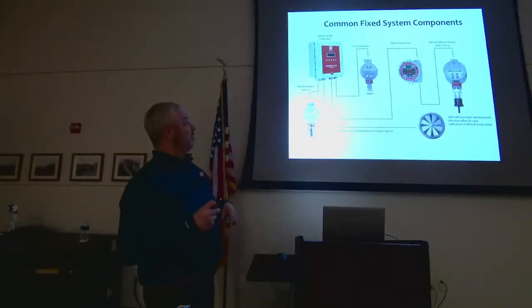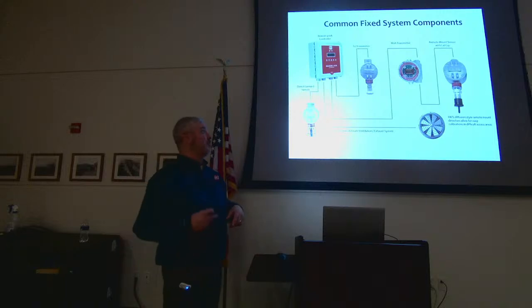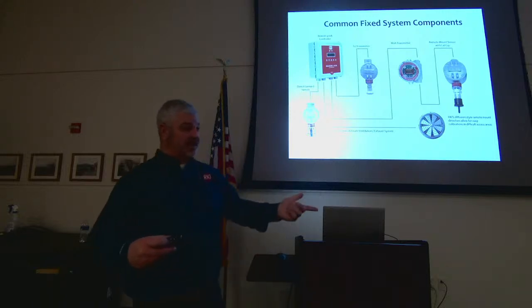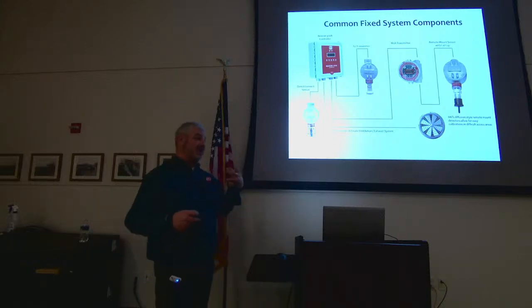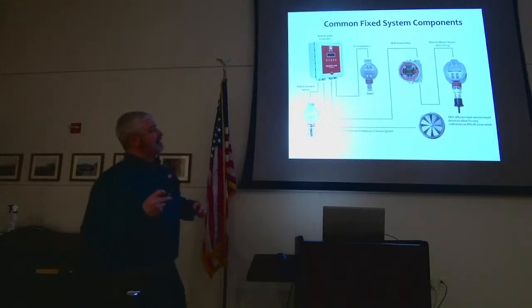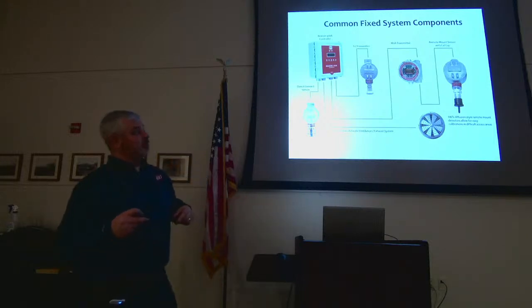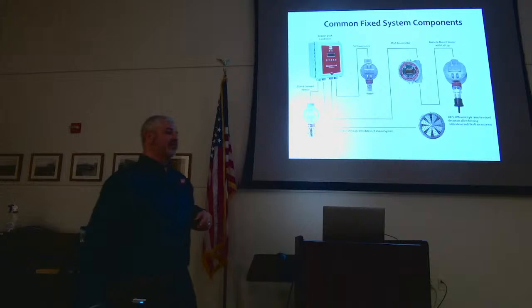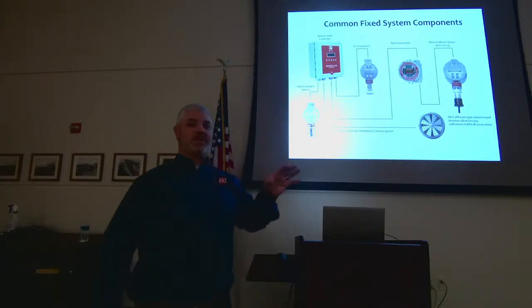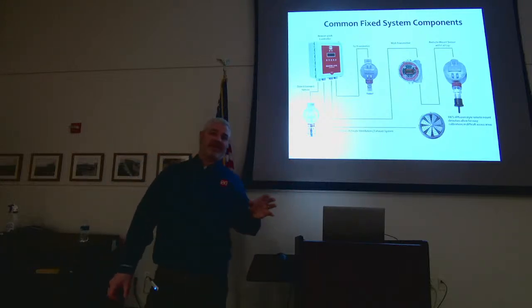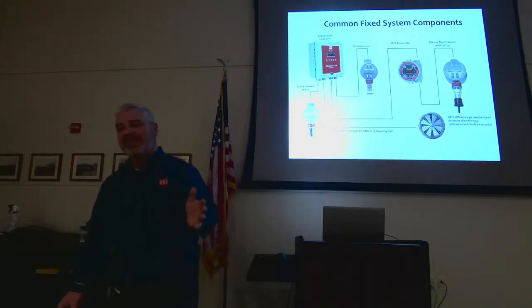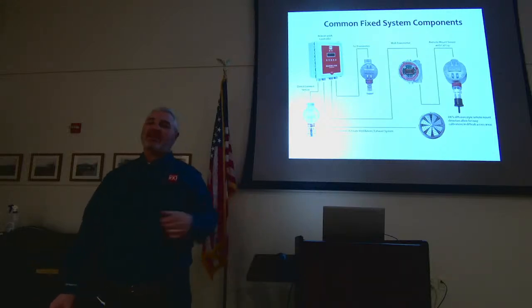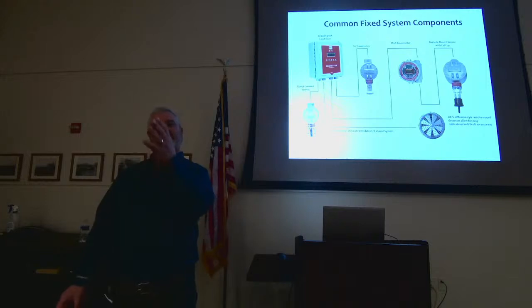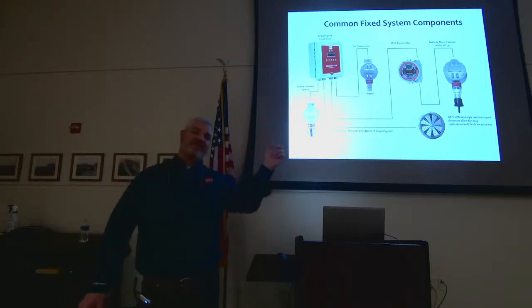On this controller, there's a little buzzer, and if you want, we could put a light on it. The people know that they should not go into that area if either is elevated, the buzzer's on, or the light is flashing. If you wanted to take that information, send it to a building security, each one of the controllers has a 4 to 20 milliamp out. Any standard security system will take that. Any fire panel will take that. Your SCADA will take that. It really is just a conduit by which you can send information.